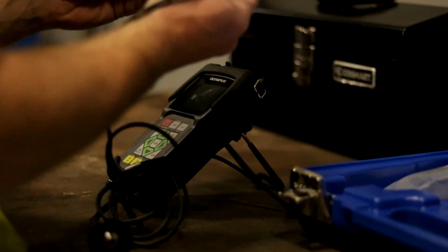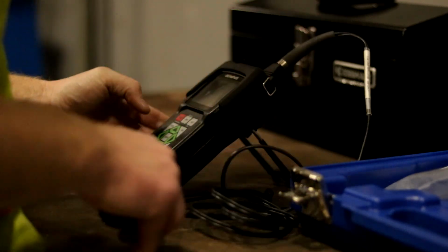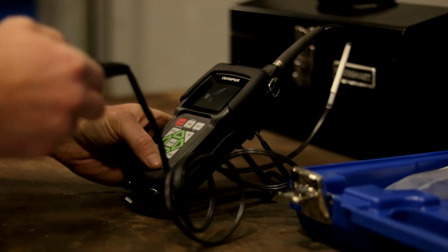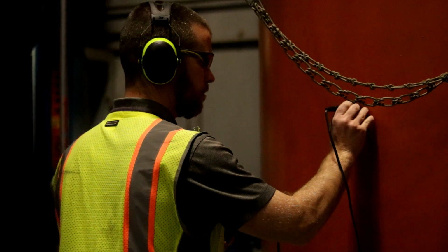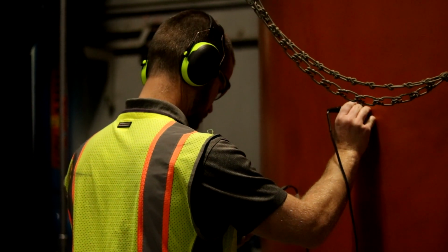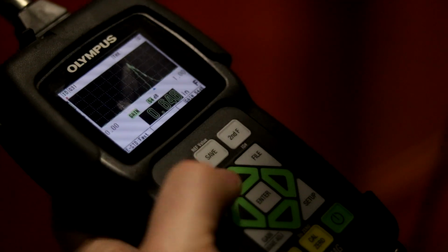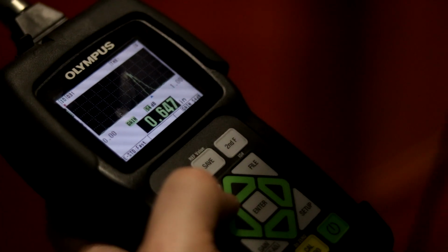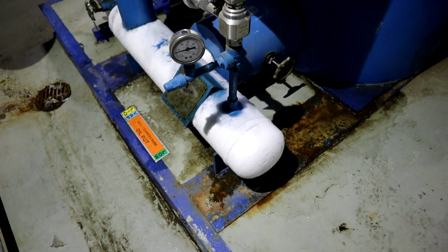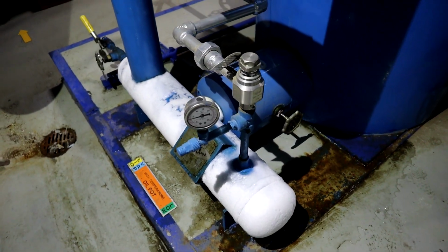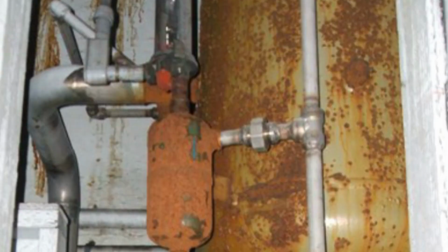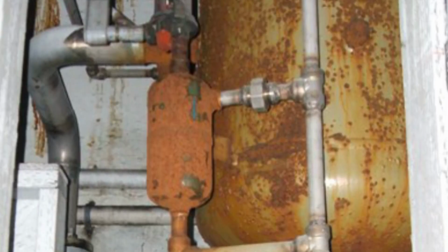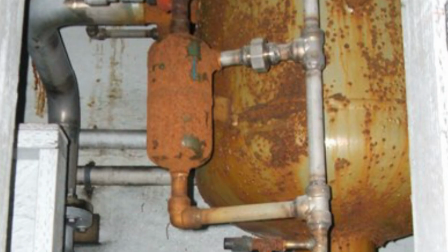Every 5th year, ammonia vessels should be assessed by a qualified inspector to determine if non-destructive testing, or NDT, should be performed. Ultrasonic thickness testing and radiographic testing are common methods of NDT employed on ammonia pressure vessels. Vessels used to collect oil should be drained as needed as part of pressure vessel maintenance. Additionally, carbon steel vessels should be cleaned and painted periodically to protect the metal surface from corrosion.